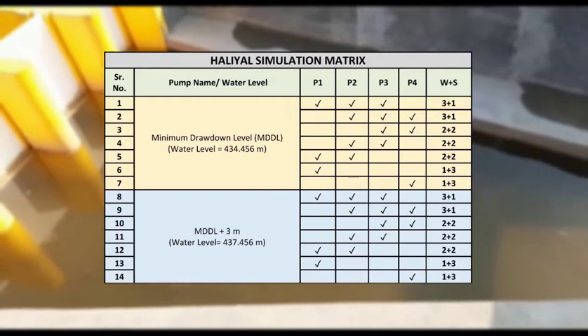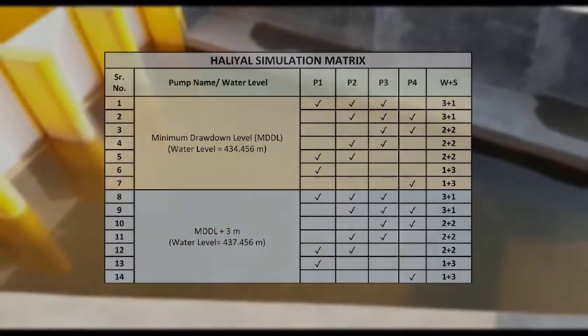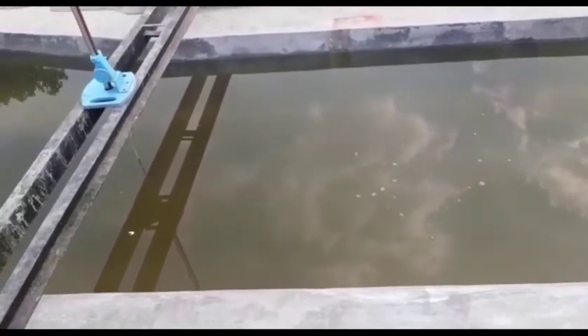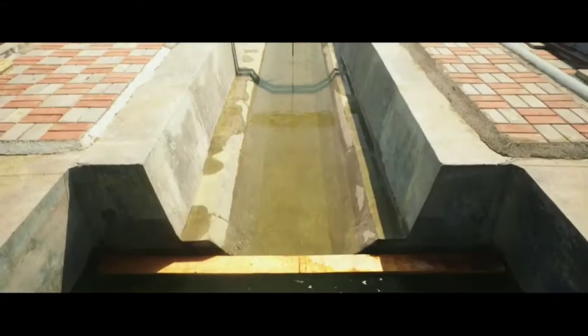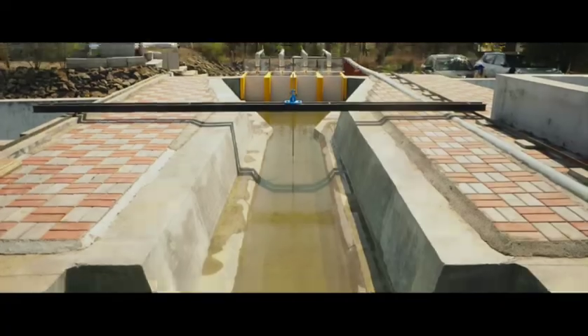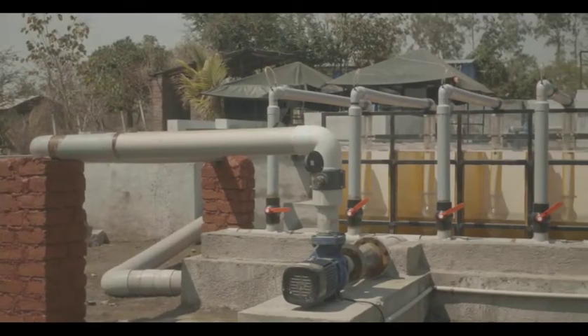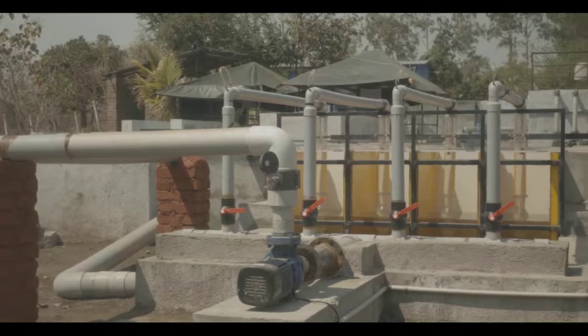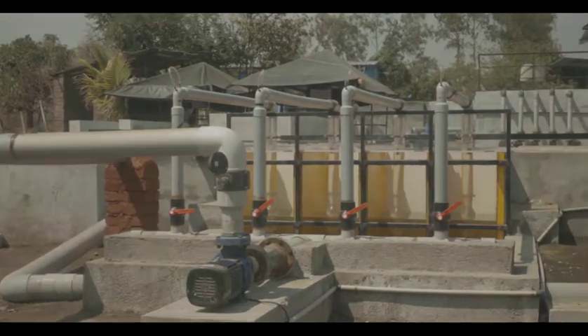The simulation matrix considered for the study is shown in the table. During experimentation, the water level is maintained in the model at MDDL and MDDL plus 3 meter for different pump operating conditions using valves, and measured with a vernier gauge of least count 0.1 millimeter to determine the water surface elevation. Flow through the suction pipe is regulated by means of a control valve for the desired pump combination. The flow was measured over a V-notch upstream of the model.